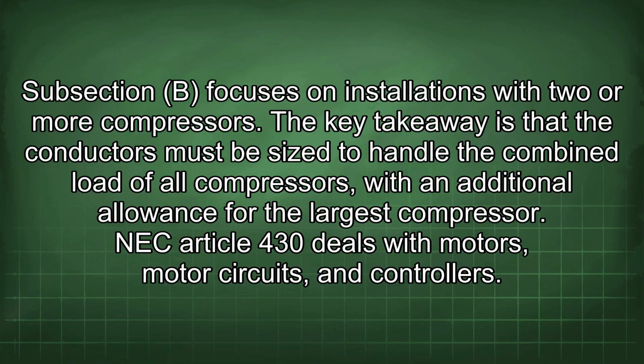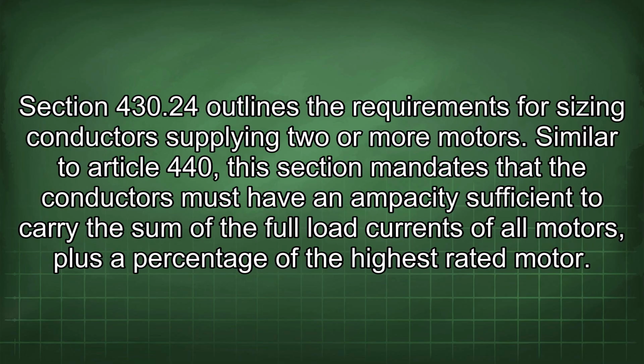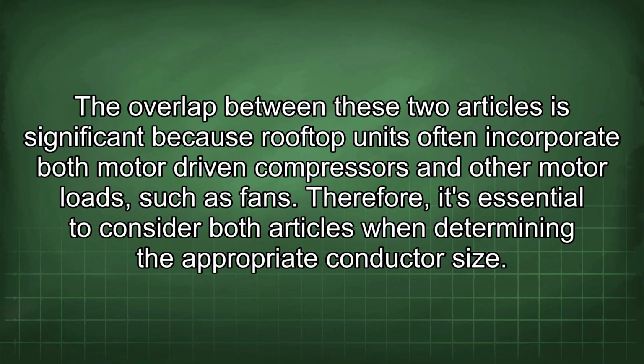NEC Article 430 deals with motors, motor circuits, and controllers. Section 430.24 outlines the requirements for sizing conductors supplying 2 or more motors. Similar to Article 440, this section mandates that the conductors must have an ampacity sufficient to carry the sum of the full load currents of all motors plus a percentage of the highest rated motor. The overlap between these two articles is significant because rooftop units often incorporate both motor-driven compressors and other motor loads, such as fans. Therefore, it's essential to consider both articles when determining the appropriate conductor size.